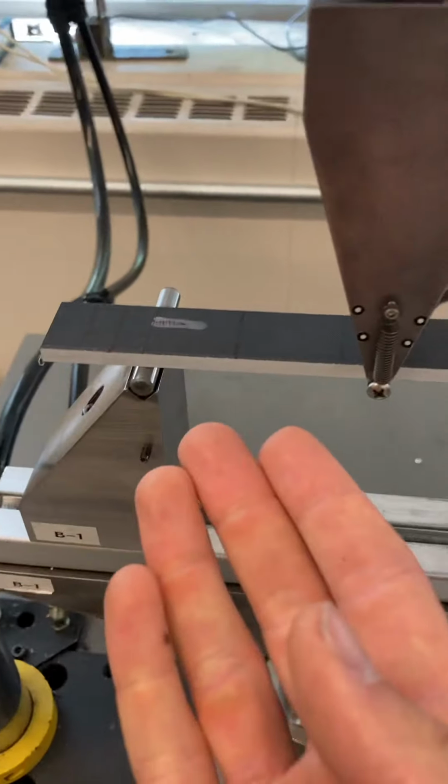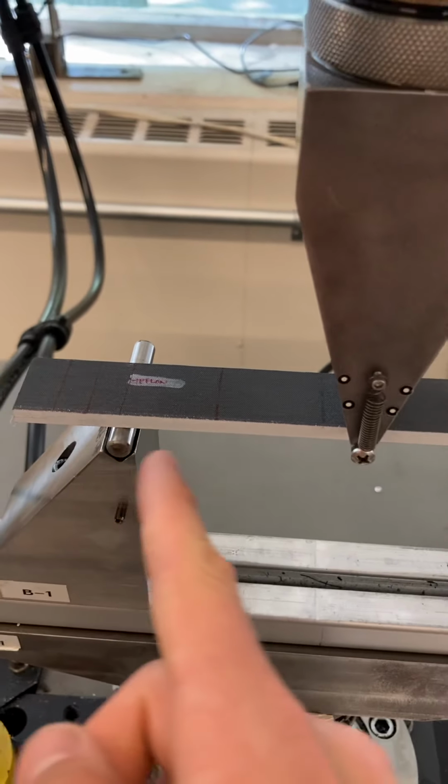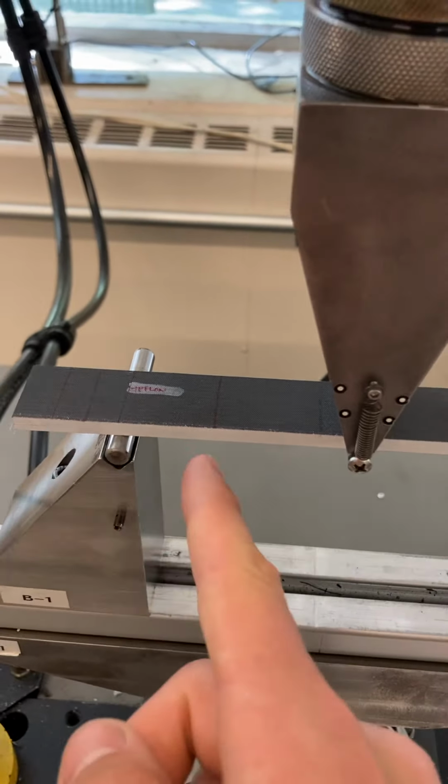And for example, we're on 35 millimeter crack length. Press start. You can see the load starts to increase. Excellent. And then you can see, well, this will start to move. This is plotting the load versus displacement in real time. But it moves pretty slowly, so it'll take a little bit for it to get there. And then you monitor this until it reaches the appropriate load for your compliance calibration test.